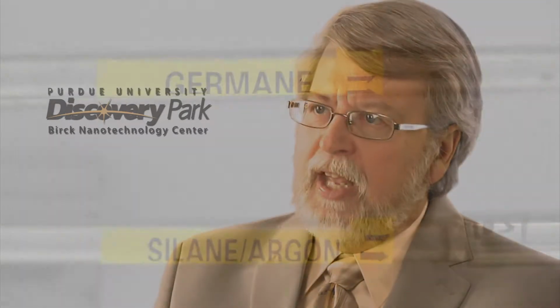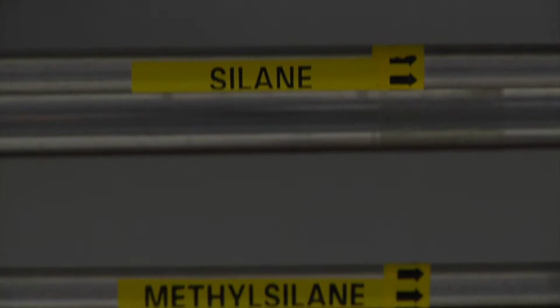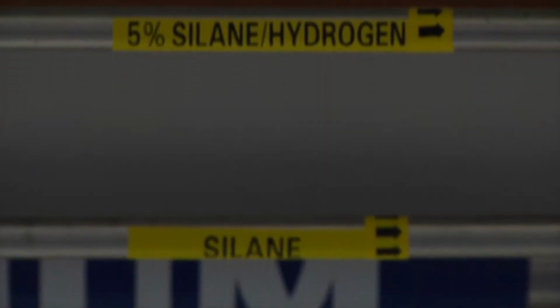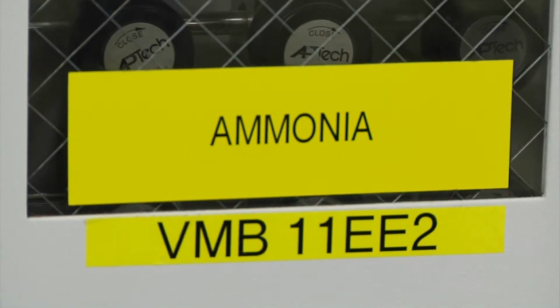That allows us to put things that are less clean down in the subfab. Again, vacuum pumps, chillers, as well as gas cabinets for inert gases. All of these can be located down in the subfab. First of all, it keeps them out of the airflow path, but also the clean room space is very valuable. So the subfab is much less costly space, and we can put a lot of these ancillary functions down there, run the piping or the wiring up into the clean room itself.